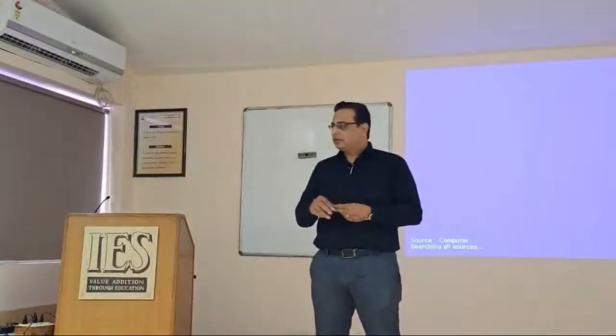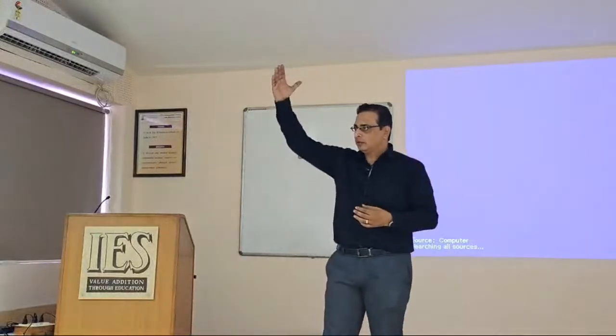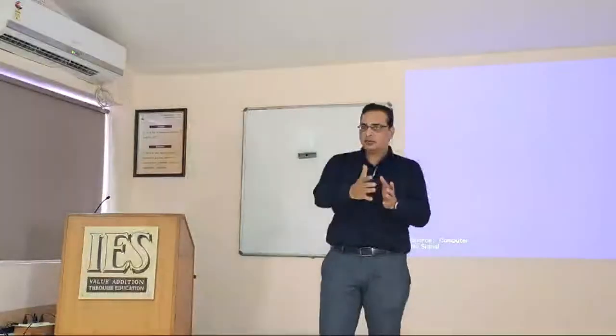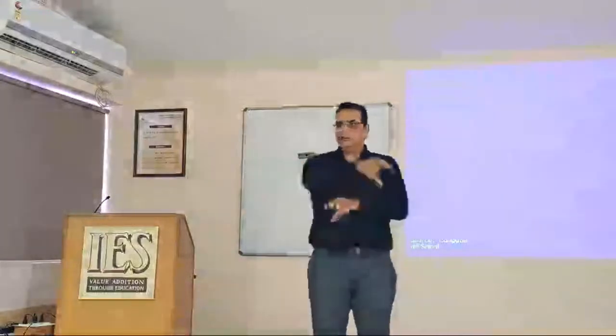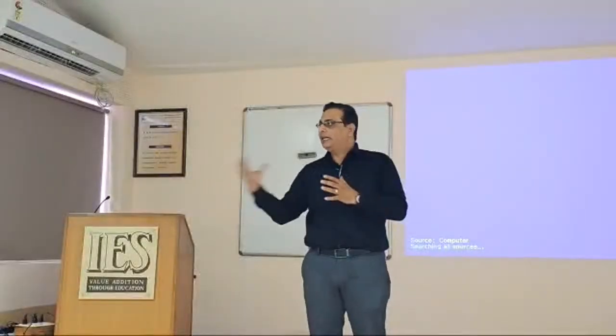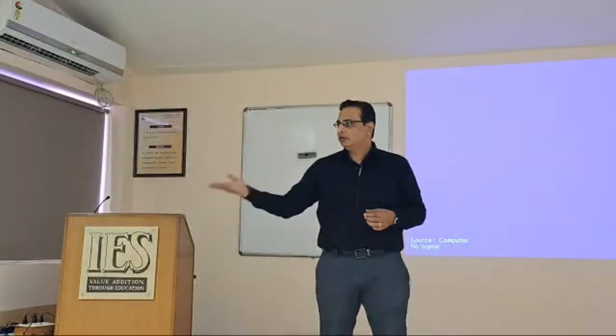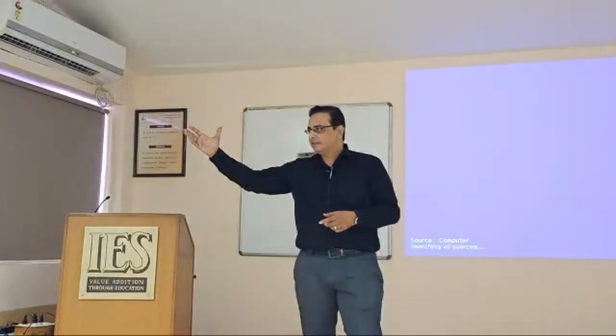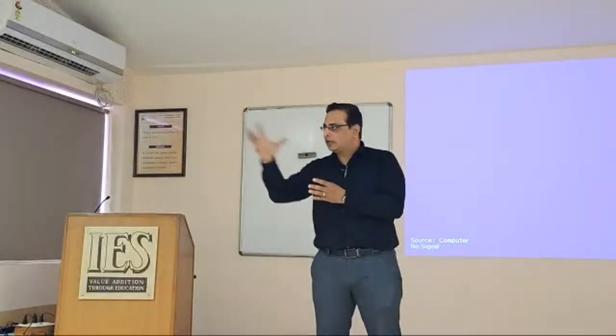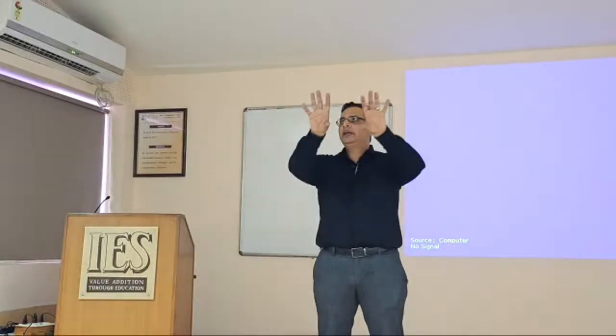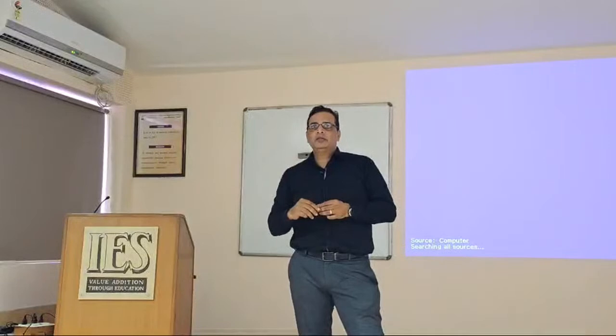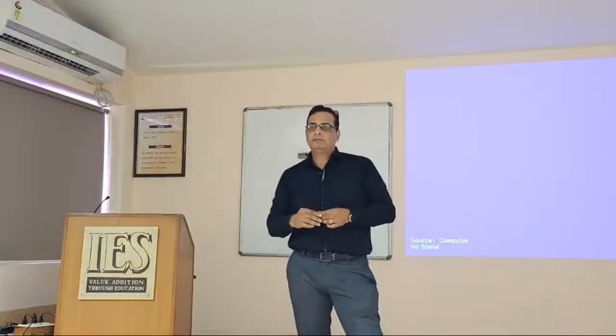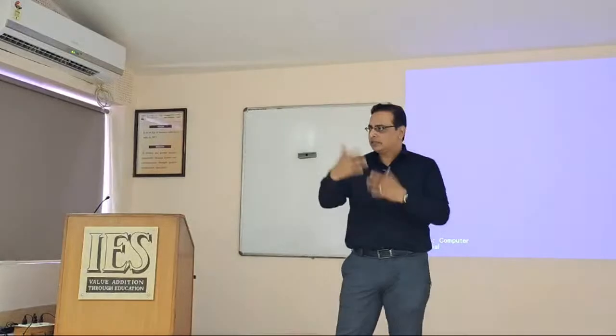So the chilled beam system has over a period been used in the north, the wide belt, in the dry climate. It has been used in Pune, areas which are outside the coastal zones, where humidity becomes a bigger part. Because if you see now, during the rains of July and August, our humidity is about 95%. Moisture comes in through the concrete structure, and this humidity will start getting into condensation. So chilled beams are used majorly in projects in the north or in dry climates.